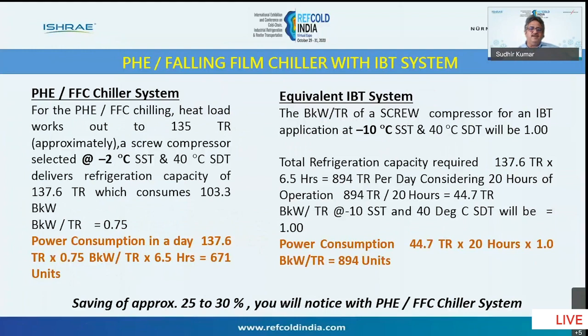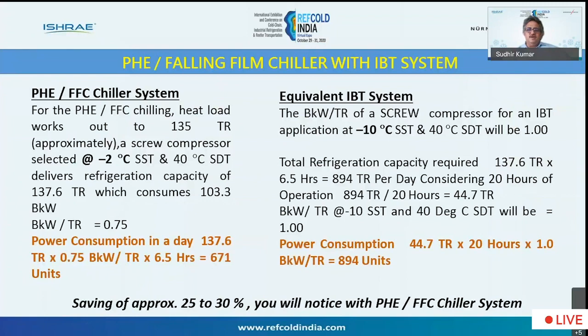So you will find that if you run a system at -2 degrees, the BKW per TR will be only 0.75. Whereas if you are running a system at -10 degrees suction, then the power consumption will be at 1 kilowatt. So if you compare this, you are approximately saving 25 to 30% of power. Yes, straight away we are saving 25 to 30% of power. But as I told you earlier, it is better to have a combination of PHE with a small IBT system.